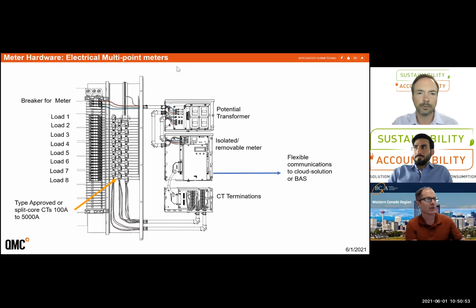Yeah, so are the CTs analog sensors, or are they a special type of CT? Is a question that's just been asked. Typically, the types of CTs we use are revenue grade type approved, and they're what's referred to as an 80 milliamp output or a 5 amp output, and those connect back into the meter themselves. They're not an analog output.